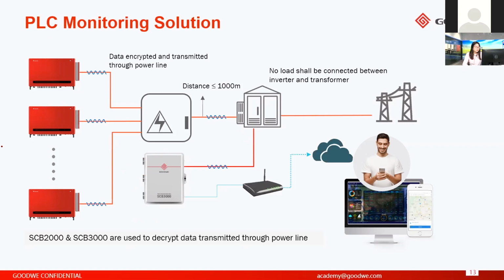As you can see from the diagram, our inverter connects via AC cables to a combiner box, and then to a transformer. On the lower voltage side of the transformer, we connect SCB 3000, and then the data is transmitted through the network to our server and presented on GoodWe SEMS monitoring platform.